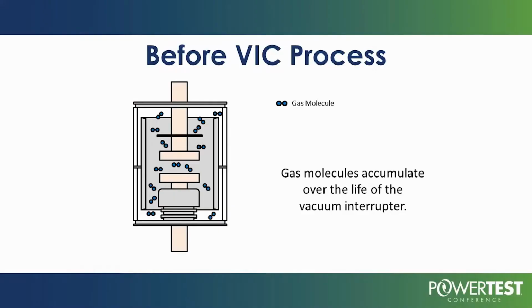It needs to be caught as early as possible, because once it gets past a certain point, the ion current gets so high that our process will not have as much effect. If you look inside the interrupter, there are a lot of gas molecules mixed inside it. When you test the interrupter, the number of gas molecules between the contacts will affect the test result. If you have a lot of gas molecules between the contacts, it's going to fail your AC/DC high pot vacuum integrity test. If you have very few gas molecules between the contacts, it's going to pass that test.